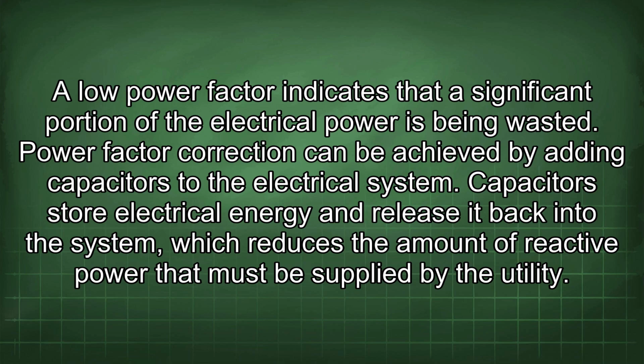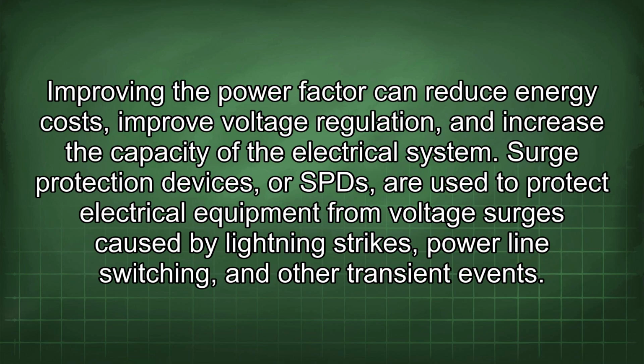Capacitors store electrical energy and release it back into the system, which reduces the amount of reactive power that must be supplied by the utility. Improving the power factor can reduce energy costs, improve voltage regulation, and increase the capacity of the electrical system.